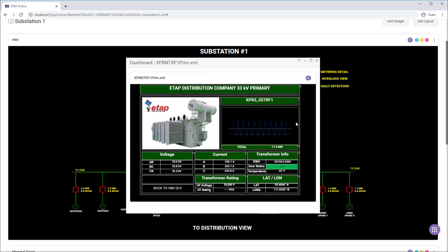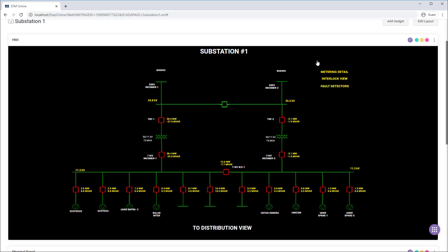In this case, it's real power, but this is also selectable as well, so anything you wish to trend you can create within this dashboard screen to specifically monitor any component that you choose. As ETAP is an intelligent SCADA, it detects configuration changes in the network, or if the operator simulates a breaker trip. So if we open this tiebreaker, even just to simulate, the configuration is detected and continuity check instantly shows when the breaker is open and parts of the system become de-energized.